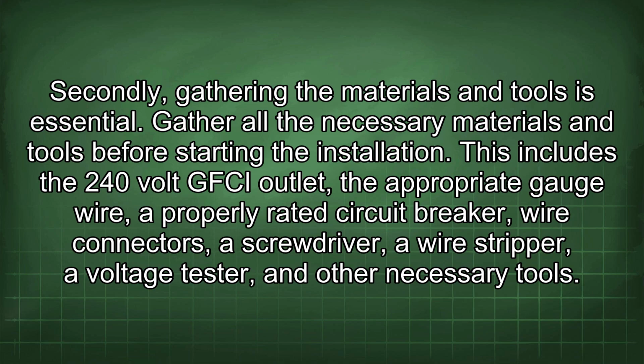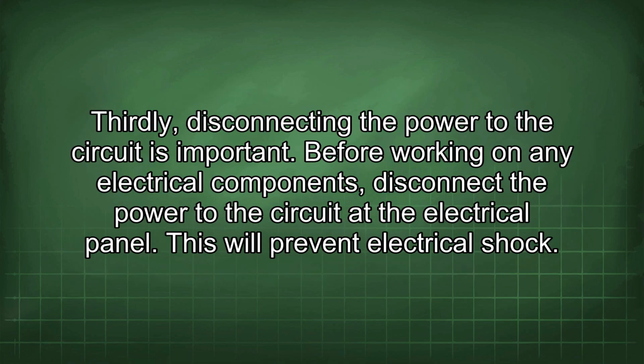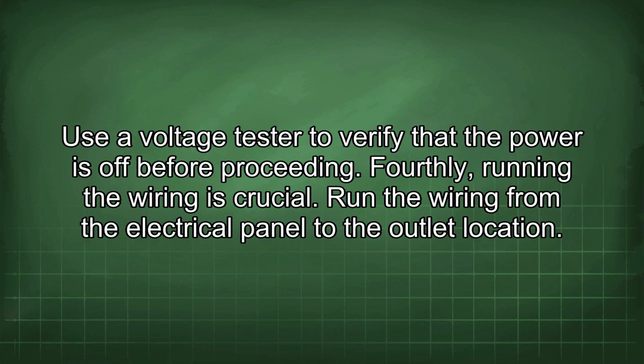Secondly, gathering the materials and tools is essential. Gather all the necessary materials and tools before starting the installation. This includes the 240-volt GFCI outlet, the appropriate gauge wire, a properly rated circuit breaker, wire connectors, a screwdriver, a wire stripper, a voltage tester, and other necessary tools. Thirdly, disconnecting the power to the circuit is important. Before working on any electrical components, disconnect the power to the circuit at the electrical panel. This will prevent electrical shock. Use a voltage tester to verify that the power is off before proceeding.